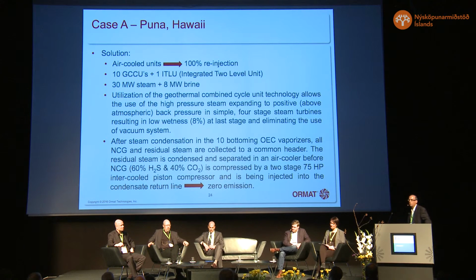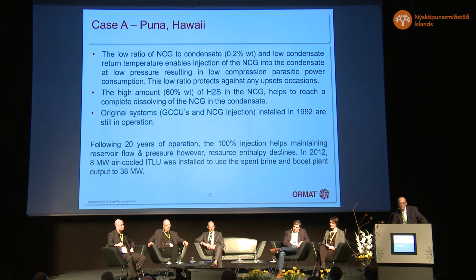Then the NCG, with a mixture of 60% H2S and 40% CO2, is compressed by a 2-stage compressor with intercooling, 75 horsepower, and it is being injected into the condensate return line, which makes the plant zero emission. What helps us to do this injection of the NCG into the condensate is, of course, the low amount of NCG, only 0.2% of the steam, the very low return temperature of the condensate, about 60 degrees centigrade, and the relatively high amount of H2S in the NCG, which is 60%.